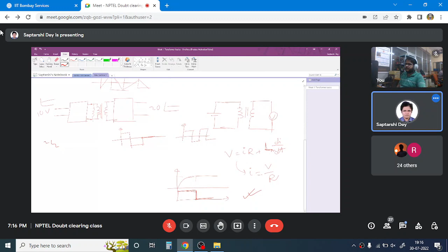Okay, sir. So what if I give DC supply instead of AC, whether the transformer is working or not? I just told you that if you manage to give, then it will be like this, but you will not gain anything out of it. You will not get any continuous flow of power if you supply DC. Is there any damage to the transformer? Yes, definitely there will be. If your voltage is large enough so that this current I equals V by R is above the RMS current rating of the windings, then it will get damaged. Thank you, sir.